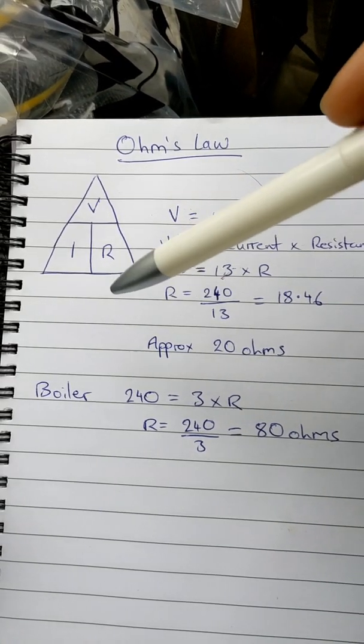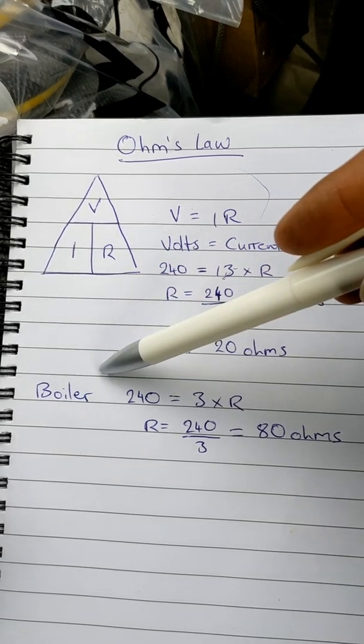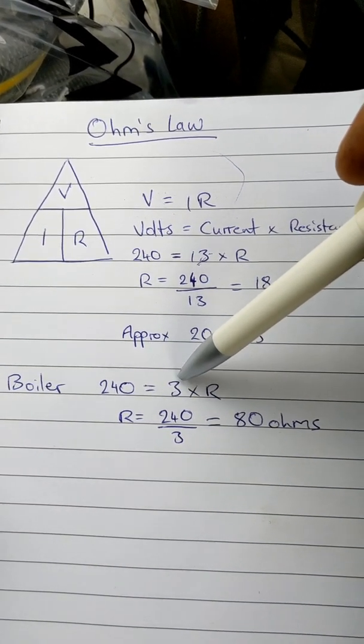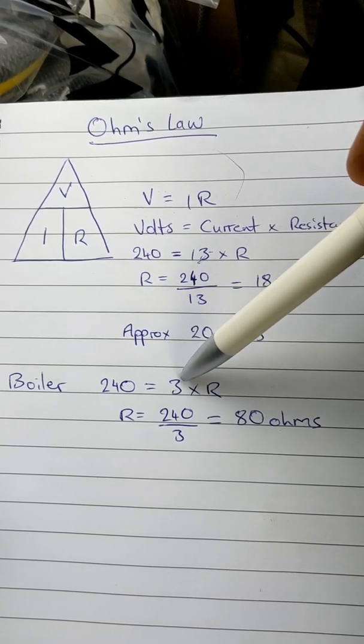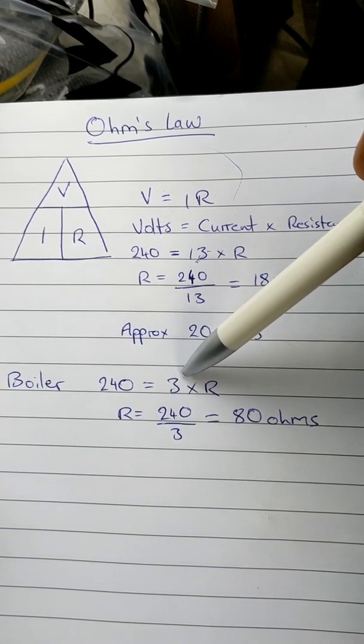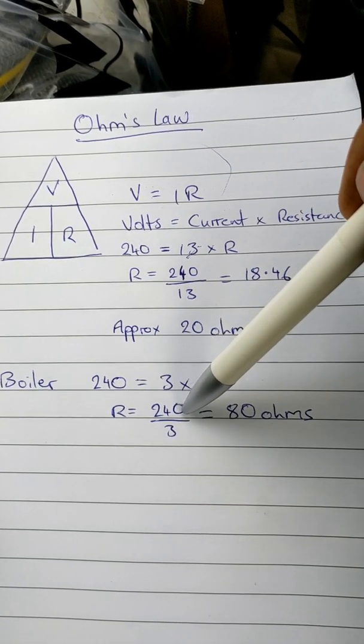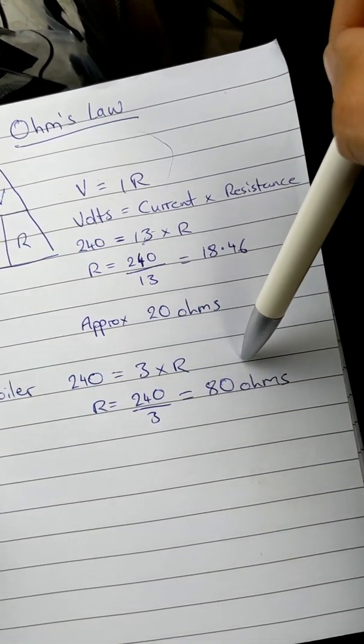Now when we're testing for short circuit on boilers, it's slightly different because boilers are protected by a 3 amp fuse. So all we're doing is we're just swapping this value from a 13 to a 3, because that's the fuse that's protecting the boiler. So you do 240 divided by 3, which gives you exactly 80 ohms.